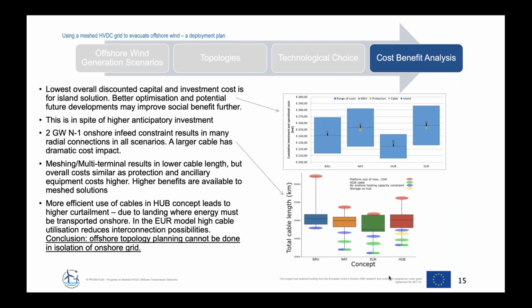The 2 gigawatt N-1 onshore in-feed constraint results in many radial connections in all scenarios. A larger cable has a dramatic cost impact, as we can see in the diagram below. Meshing multi-terminal connections result in lower cable length, but the overall costs of the system are similar, as protection and ancillary equipment costs are higher.